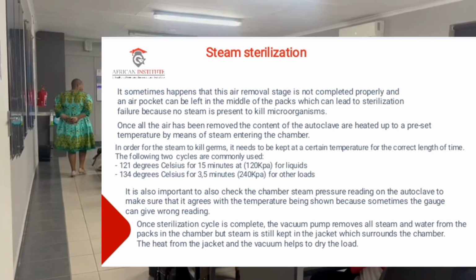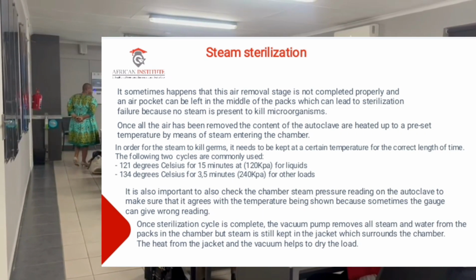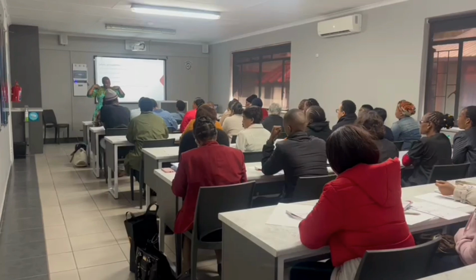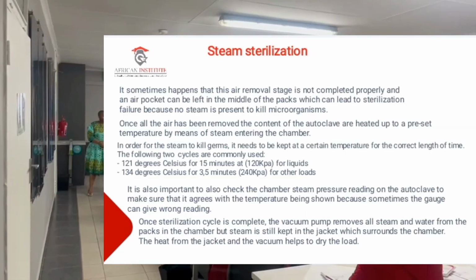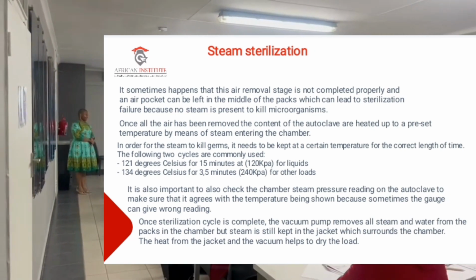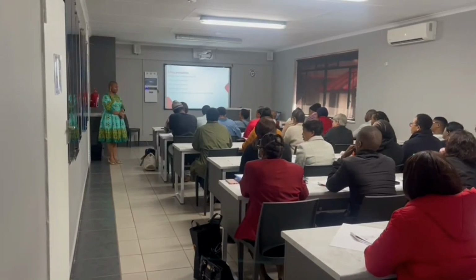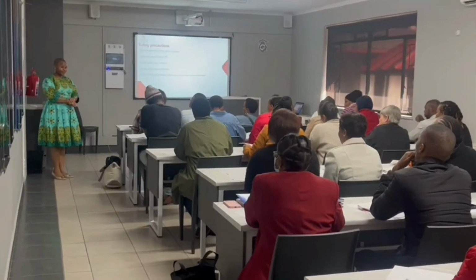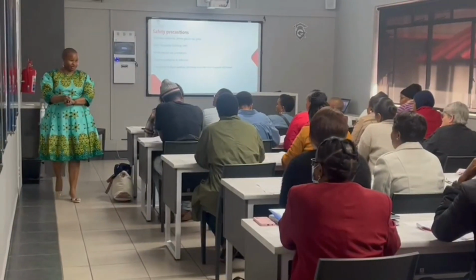In order for the steam to kill germs, it needs to be kept at a certain temperature for the correct length of time. The following 2 cycles are commonly used: 121 degrees Celsius for 15 minutes at 120 kilopascal pressure for liquids and rubber and glass, and 134 degrees Celsius for 3.5 minutes at 240 to 250 kilopascal pressure for all the other loads, which is your soft pack and your steam loads, including your containers.